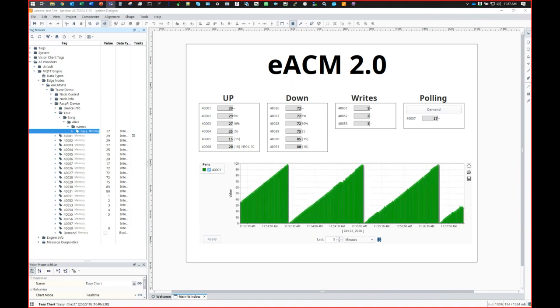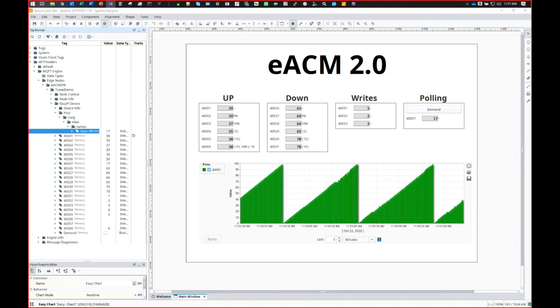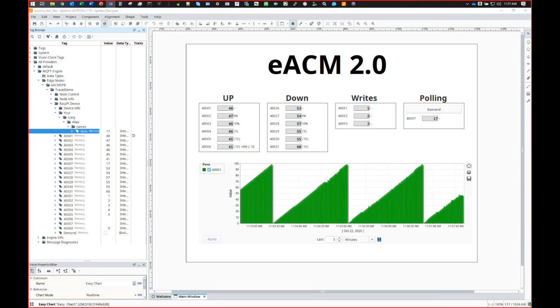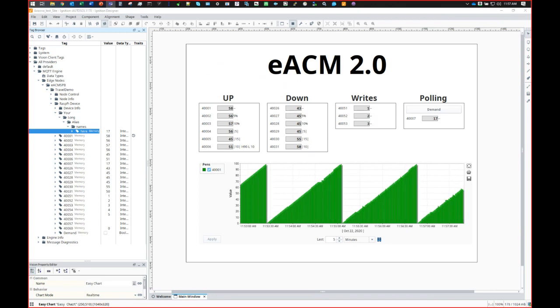What happens at 23.51 days of backfill? We start deleting the oldest records and replacing them with the newest records. So how much you can backfill depends on how much space is on your box and how many tags you have set backfill to true for. If you're pulling 2,200 tags and you hit backfill, you probably have more than a week, because all 2,200 of those tags are probably not changing value. Your vals probably are not changing value every time they pull, or your GCs are probably not changing value. So I hope I answered that question.